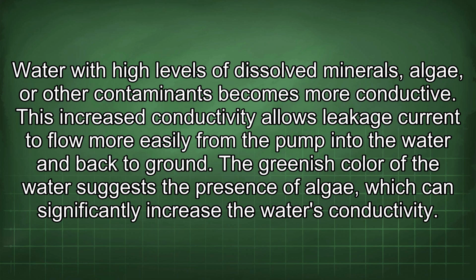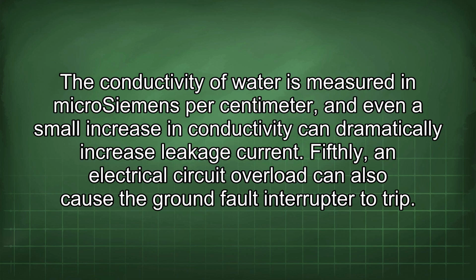Water with high levels of dissolved minerals, algae, or other contaminants becomes more conductive. This increased conductivity allows leakage current to flow more easily from the pump into the water and back to ground. The greenish color of the water suggests the presence of algae, which can significantly increase the water's conductivity. The conductivity of water is measured in microsiemens per centimeter, and even a small increase in conductivity can dramatically increase leakage current. Fifthly, an electrical circuit overload can also cause the ground fault interrupter to trip.